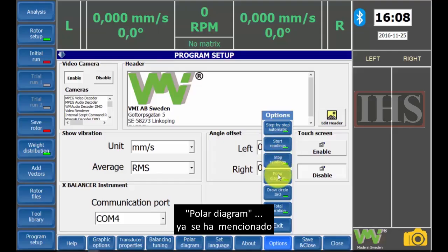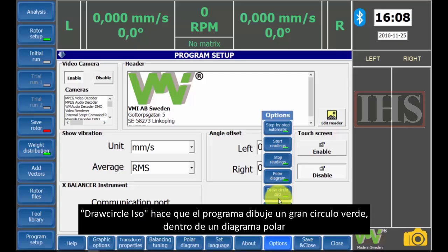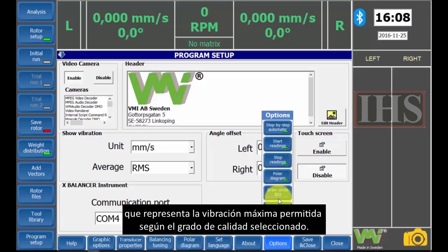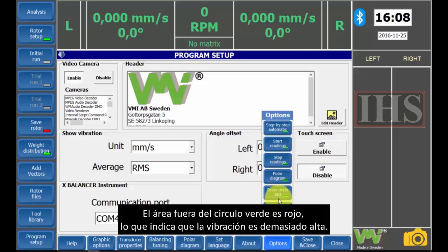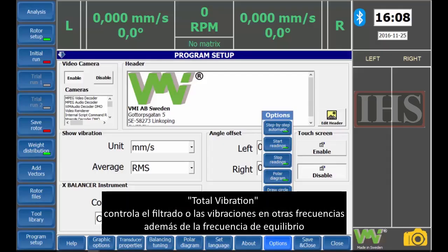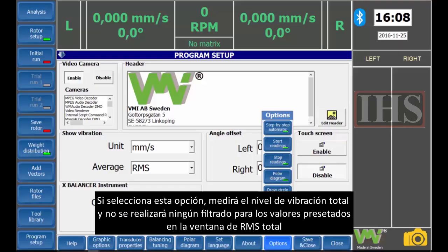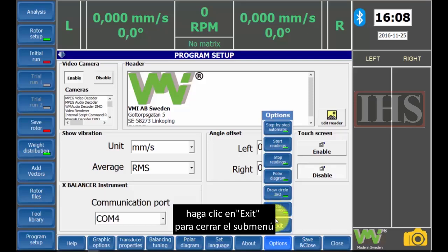Polar diagrams has already been mentioned. Draw Circle ISO makes the program draw a gray-green circle inside the polar diagrams, representing the allowed maximum vibration according to the selected quality grade. The area outside the gray-green circle is colored red, implying that the vibration is too high. Total vibration controls filtering of vibrations at other frequencies than the balancing frequency. If you select this option, the total vibration level is measured and no filtering is performed for values presented in the total RMS window. Click Exit to close the submenu.